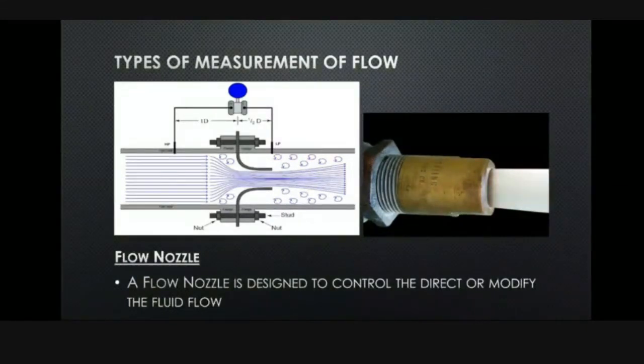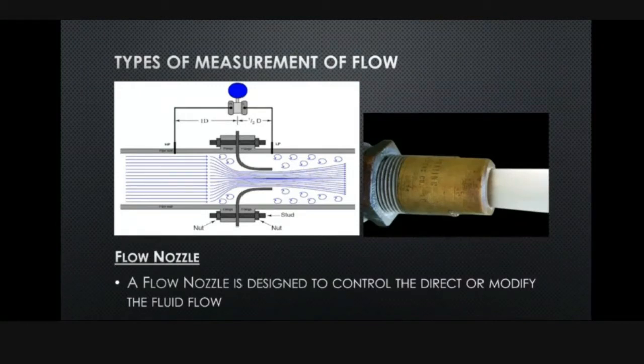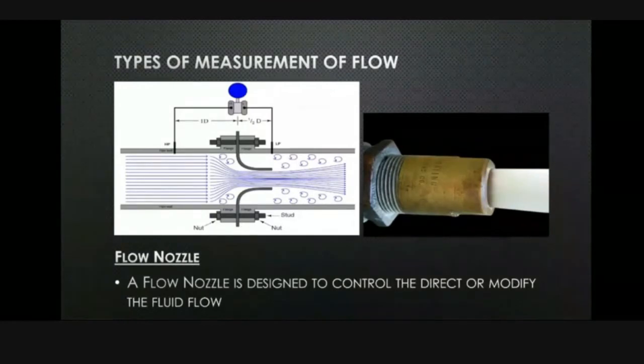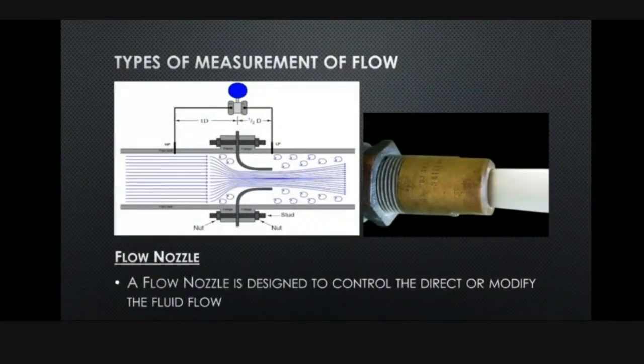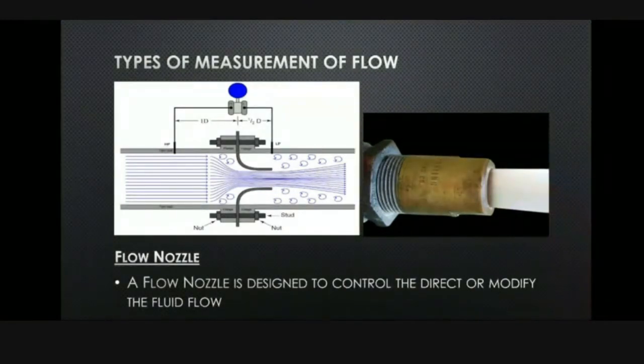Application of flow nozzle. First, it is used to measure flow rates of liquid discharged into the atmosphere. Second, it is usually used in situations where suspended solids have a property of settling. Third, it is widely used for high pressure and temperature steam flows. Advantages of flow nozzle. First, installation is easy and cheaper compared to the venturi meter. Second, it is very compact. Third, it has a high coefficient of discharge. And disadvantages of flow nozzle. First, pressure recovery is low. Second, maintenance is high. Third, installation is difficult when compared to the orifice flow meter.